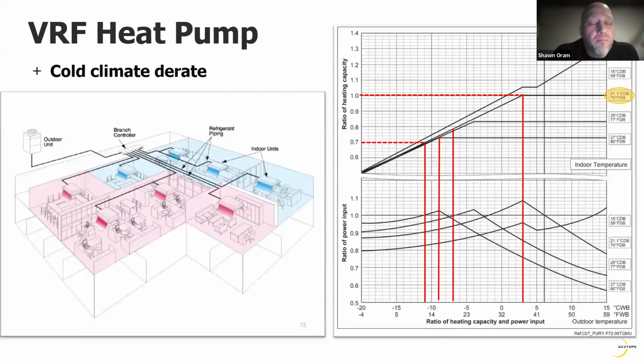Just a little detail about VRF heat pumps. There's an outdoor unit over on the left. It's connected by refrigerant to a branch controller manifold, and then those distribute to fan coils. Like I mentioned, this project used a radiant floor instead of fan coils. So there's a refrigerant to water heat exchanger, but there are some zones that are fan coils, and I'll talk about that a bit more. Just wanted to show the derate and how the heat pump was selected. Nominal rating is about 38 at 38 degrees for this particular heat pump model. As the temperature drops, you get reduced capacity. So this was sized for that extreme, and it's about a 30% hit on capacity.